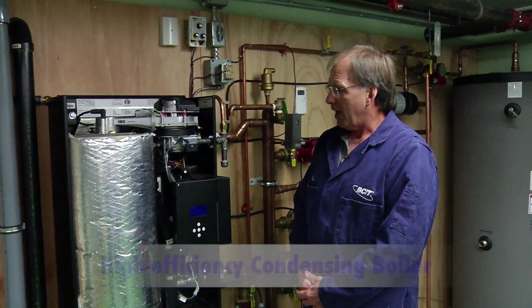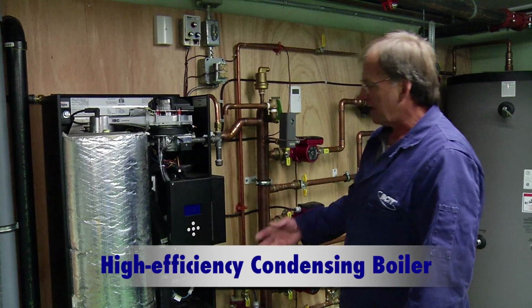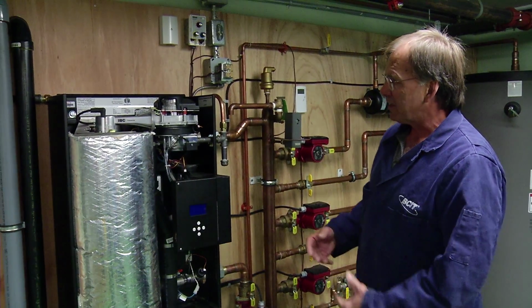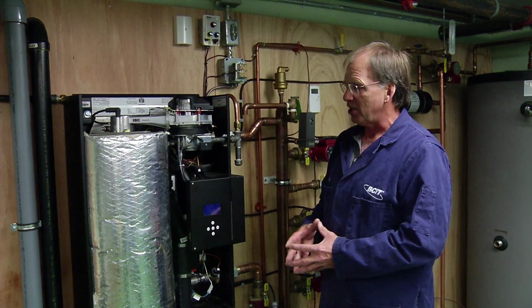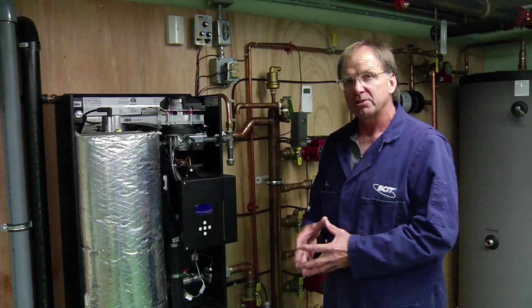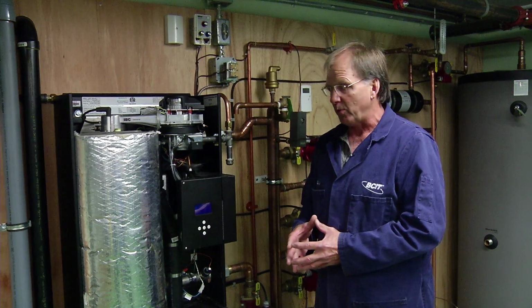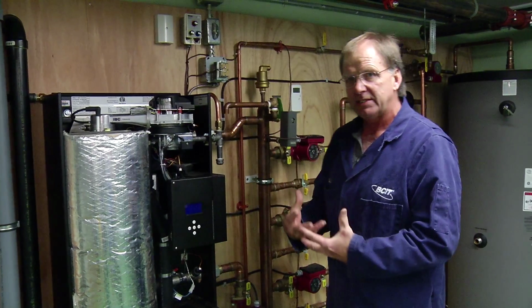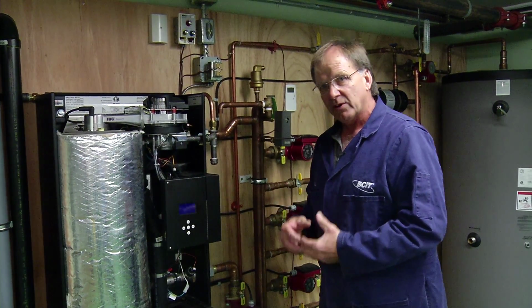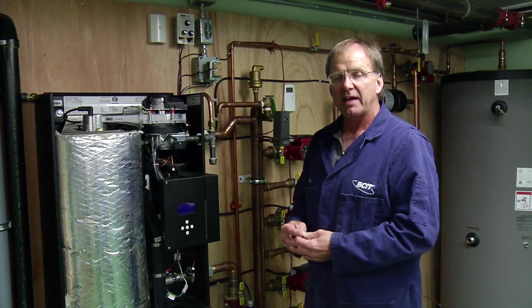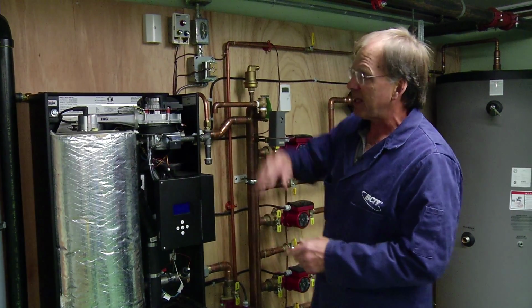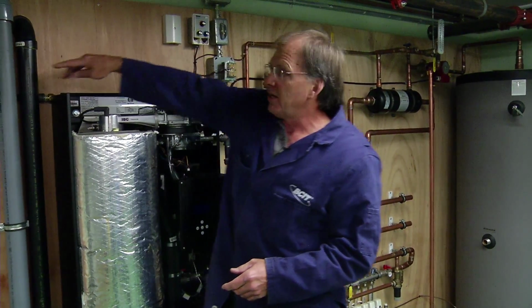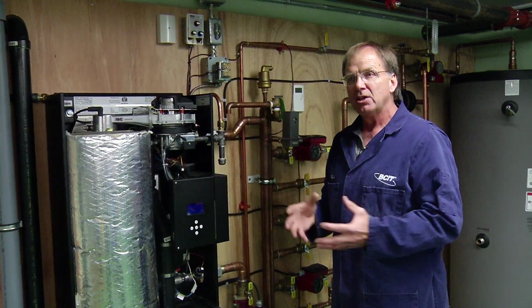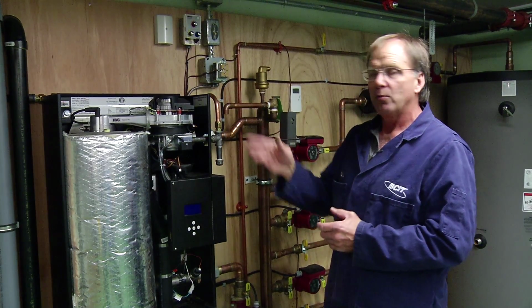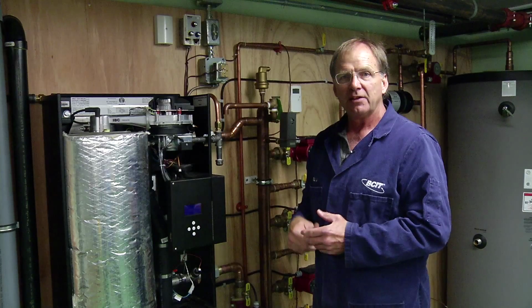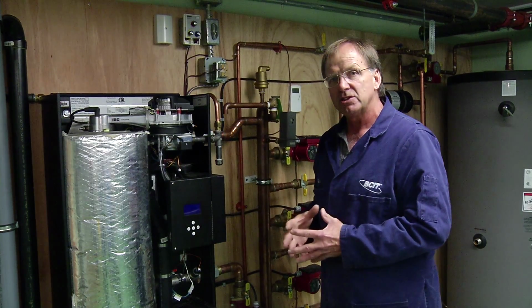In the lab, we've installed a high efficiency boiler. What it does is it actually uses condensing technology to produce 10 to 15% more efficiency than a standard atmospheric boiler. It does that because it actually condenses the flue gases, regains the latent heat from that condensing, and then takes the exhaust to the two vents over on the other side. These are just plastic vents because instead of being 300, 400 degrees as in traditional venting, we now can use a special plastic that is about 90 degrees. So you can see the difference in where the heat is.